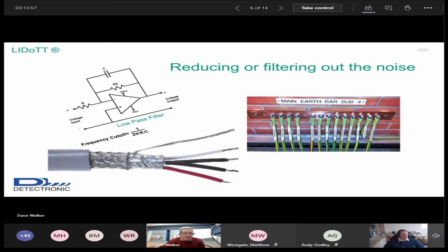Yes, we can do it in electronics. We can use what are called low pass filters or high pass filters. So that's frequencies. If you've got a mains source, a 240 volt or a 415 volt mains supply, what's causing you problems is going to be transmitting at a frequency of around 50 to 60 hertz, not kilohertz, but hertz. So you'd want a high pass filter, i.e. you're going to block out that 50 hertz and then pass forward any high frequencies. That's basic electronics, and for any manufacturer of level, velocity and flow monitoring equipment, that's not something new. That's what we do in the background anyway. We can also purchase low pass and high pass filters to put onto the actual mains supply themselves. So that's another way of reducing it.